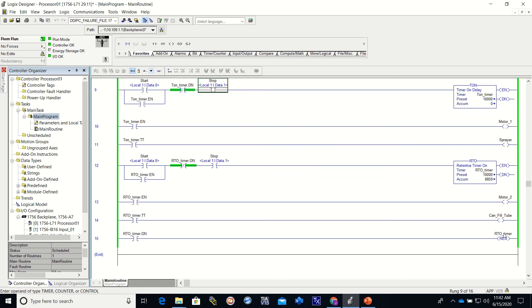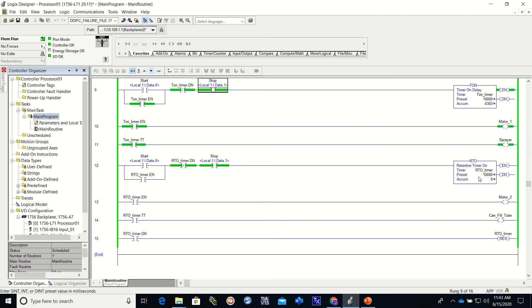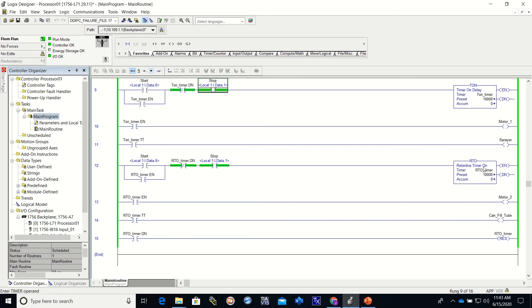And since this reset did not come on because the RTO was not done, we will not reset. Now I'm going to go ahead and restart it and you'll see that it did that. So that's how an RTO works. Remember it is retentive. So if you want to save the amount of time that you have accumulated, that's where you would use an RTO as opposed to a TON.